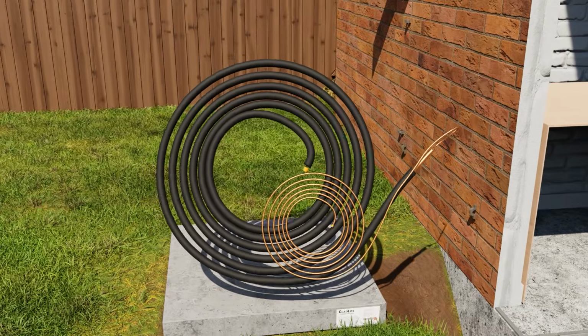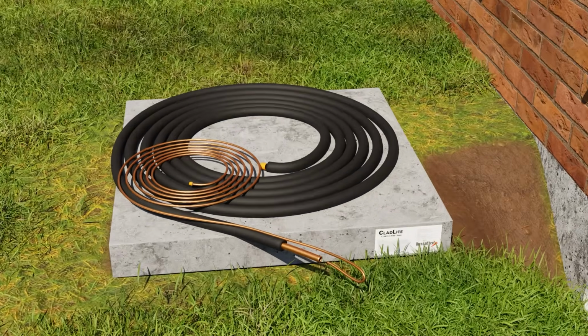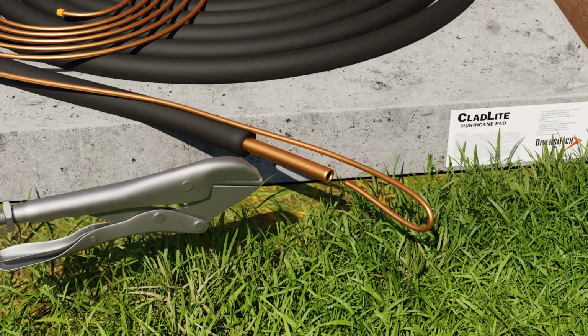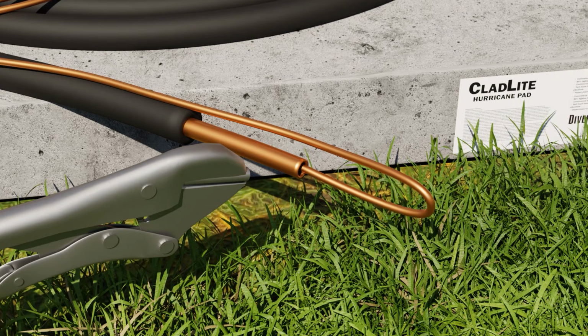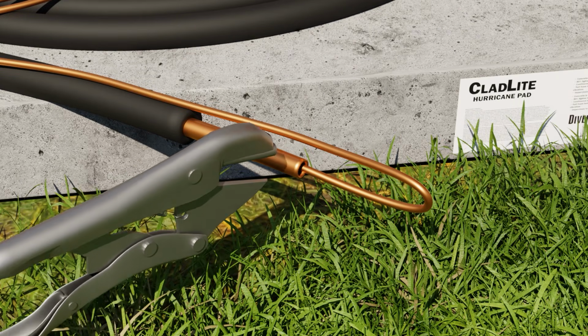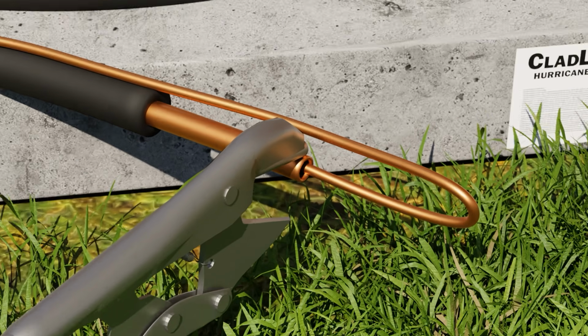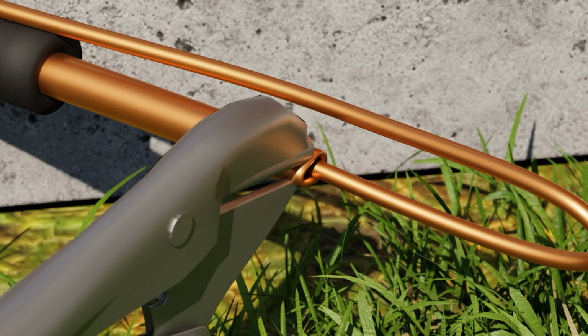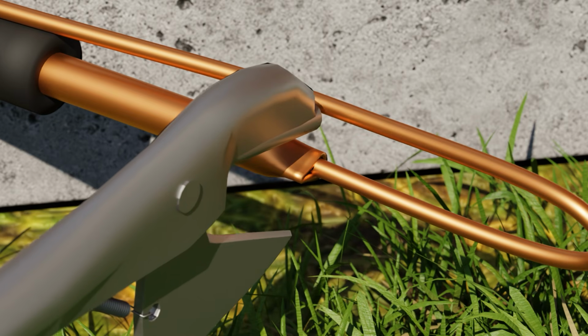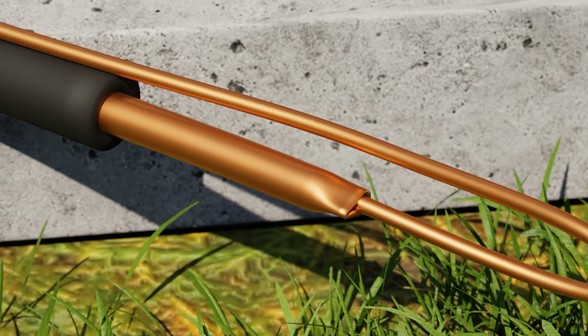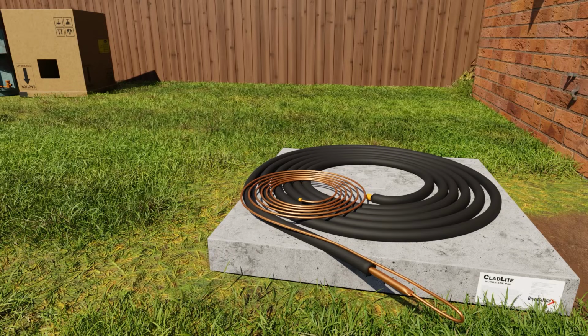Now we're going to show preparing the copper to push it. One of the best practices we found is looping your liquid line around and pinching it down into your suction line. We find this to be one of the best practices even if you're running attic copper because of the possibility of caps coming off and the copper becoming contaminated. The loop in the liquid line makes it a little easier to pull through. But again, you can push the bare ends, just make sure you braze them shut before you do so. The plastic or rubber caps can easily come off, which can result in the line set being contaminated.